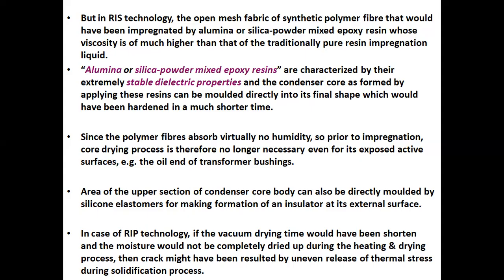In case of RIP, that is resin impregnated paper technology, if the vacuum drying time is shortened and the moisture is not completely dried out during the heating and drying process, then cracks might result from uneven release of thermal stress during the solidification process. This is the disadvantage of using RIP technology.